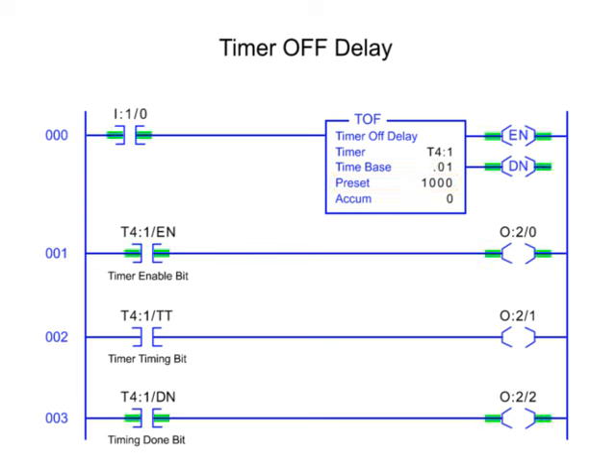The timer off delay sets the enable and done bits when input conditions are true. When the input conditions change to false in the timer off delay instruction, the timer timing bit goes true. As the accumulated value reaches the preset value, the done and timer timing bits turn off.